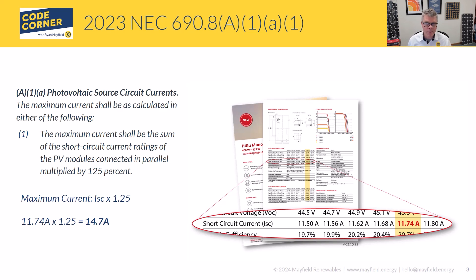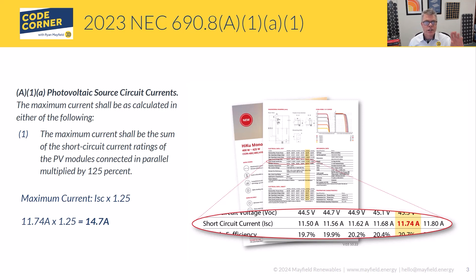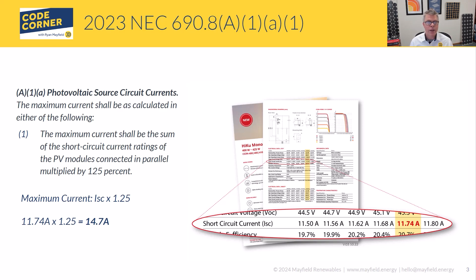First is A1A, which is actually broken into two subparts. I'm going to focus on the first one. The correction factor we're going to apply is to our PV system short circuit current value. On this slide we're showing you a spec sheet from a PV module manufacturer — you can see there in that bubble callout that 11.74 amps is the rated short circuit current at standard test conditions. What A1A1 is saying is we take that value and multiply it by 125%, and that becomes our maximum circuit current value.